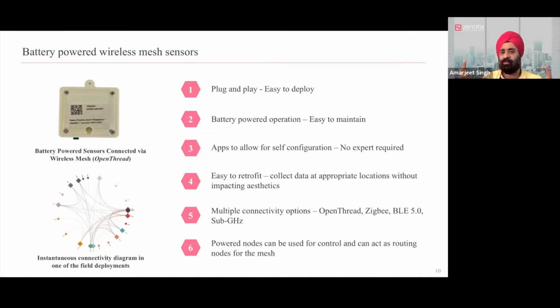This battery powered sensor simply runs on two AAA batteries, can be put into ambient environment as well, right? So one of the things that BMS completely misses out is that it doesn't go to the actual areas where you are controlling, let's say, the HVAC for, right? So only if those areas have room thermostats installed, which is again a rare thing in the BMS systems or even in the HVAC systems designed in the Indian context. Typically, the DDC in the BMS room would sit in an AHU room and is only looking at the return air temperature fed from all the rooms in the zone that are served by a single AHU. And one is not really looking into whether the occupant in each of those rooms is getting the necessary comfort or not, right?